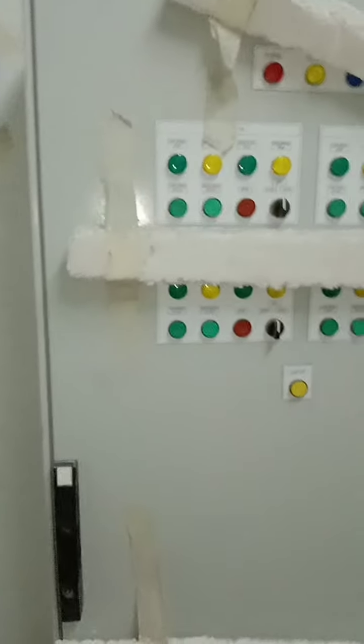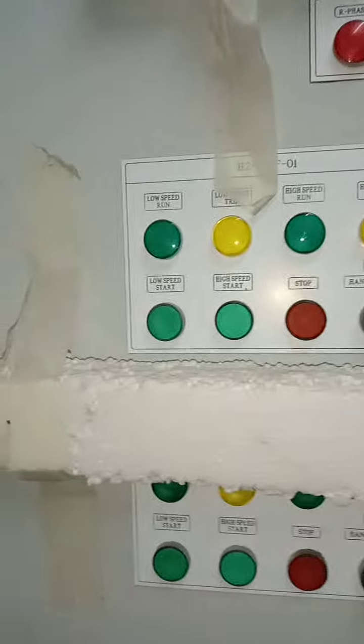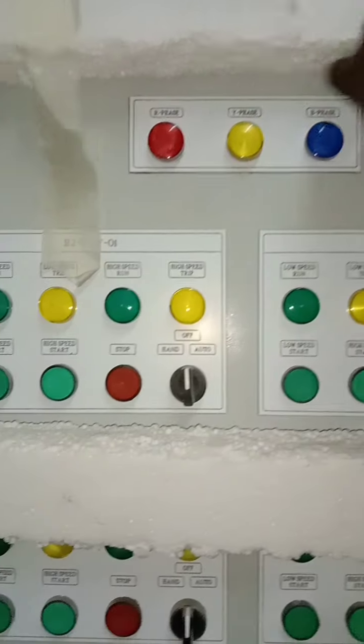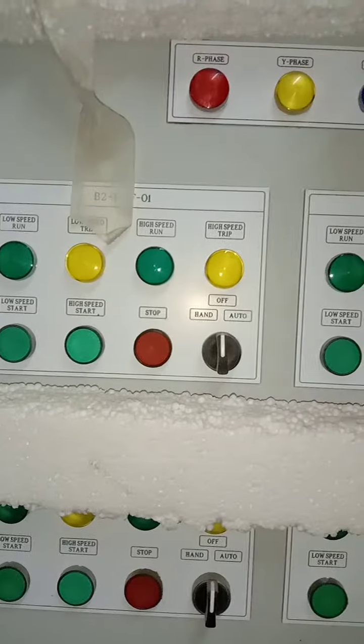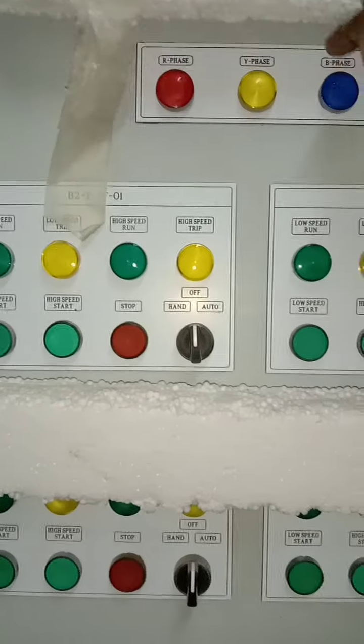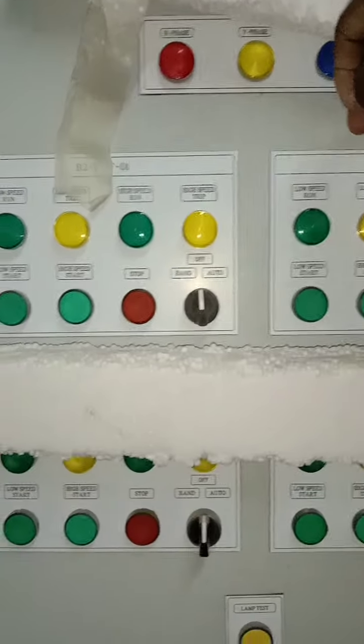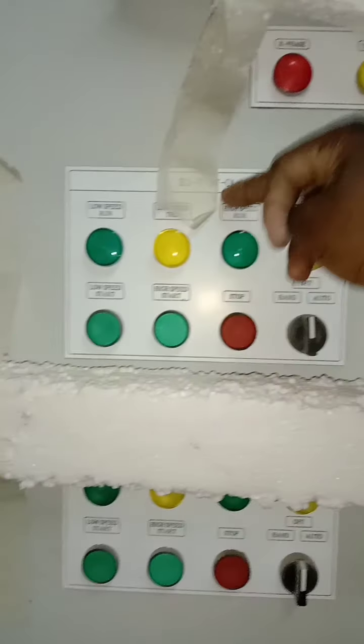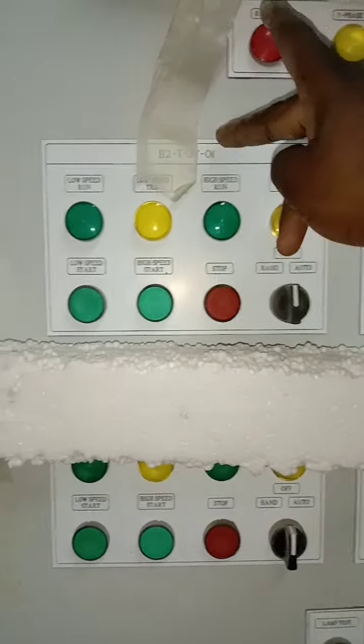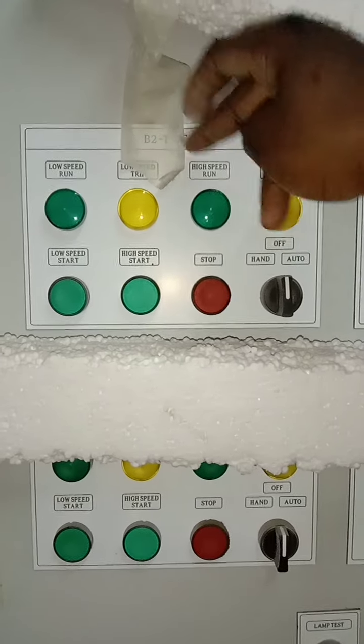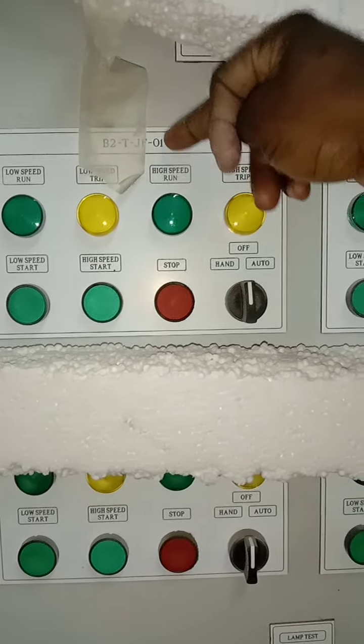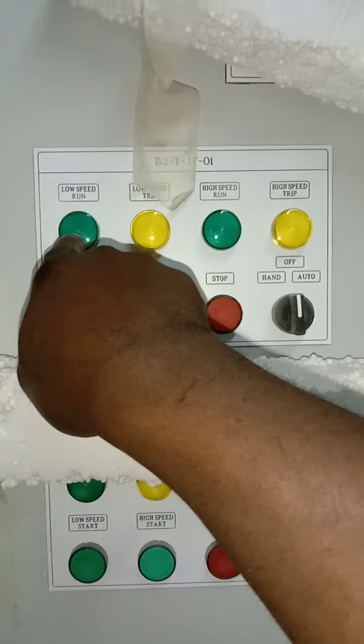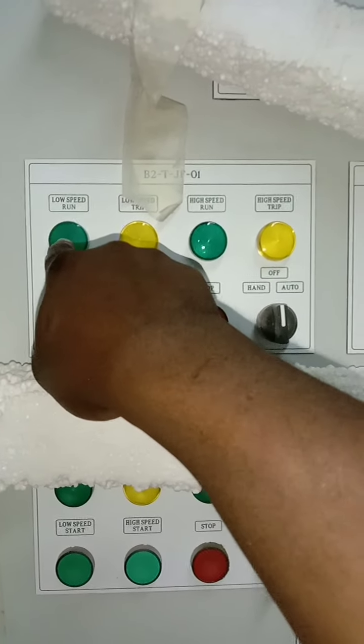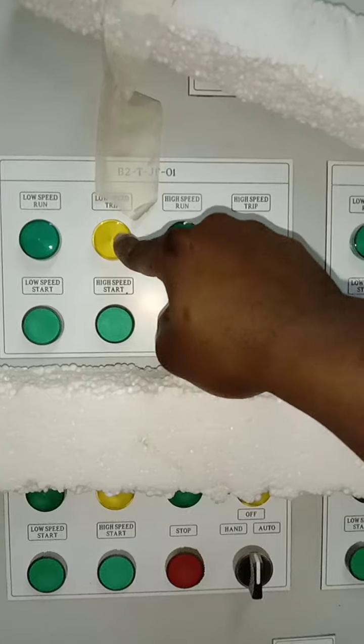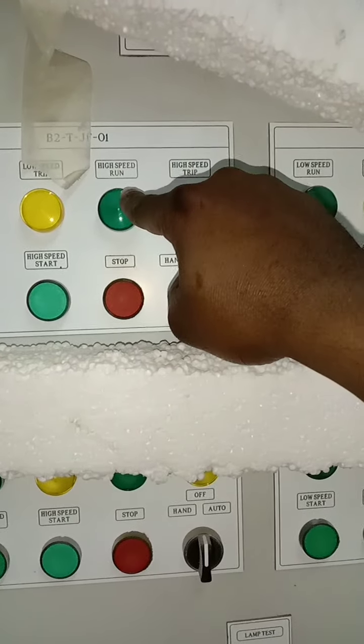As you can see, on the outer part of the panel, we have three indicator lights, R, Y, B. As I did mention, it's used to indicate the healthiness of the supplies. On the side here, the first part that you see is for one particular jet fan, which is B2TJF01. And then it has an indication light for low speed run, low speed trip, high speed run, and high speed trip.